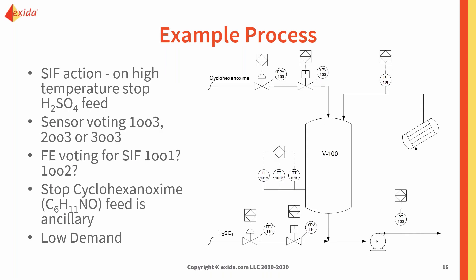Here's an example process — an intermediate reaction for the production of Nylon-6, simplified in this diagram. Our goal is to stop the reaction on high temperature. We have two streams feeding in: cyclohexanoxime at the top and sulfuric acid at the bottom. Our initial definition of the safe state is stopping the sulfuric acid feed. We have three temperature transmitters, but one question we'll ask is whether we really need three to meet our SIL target, or if we can do it with fewer.